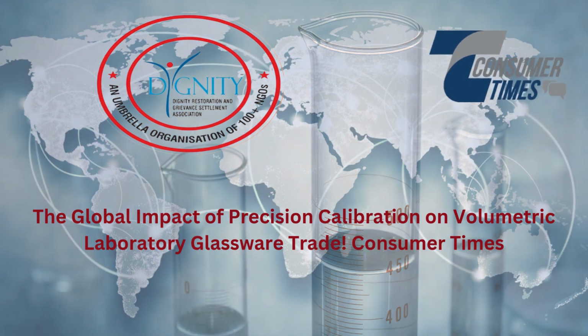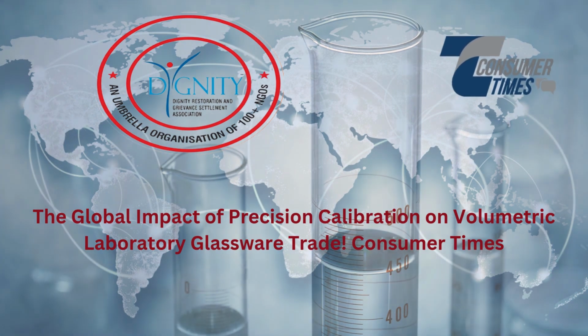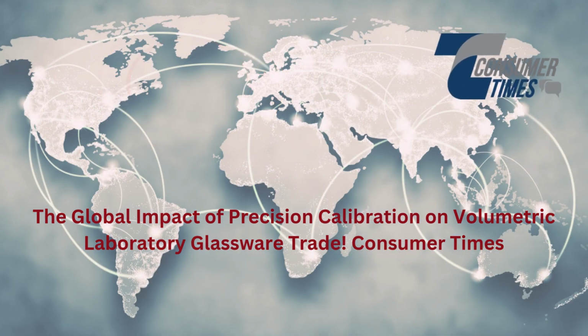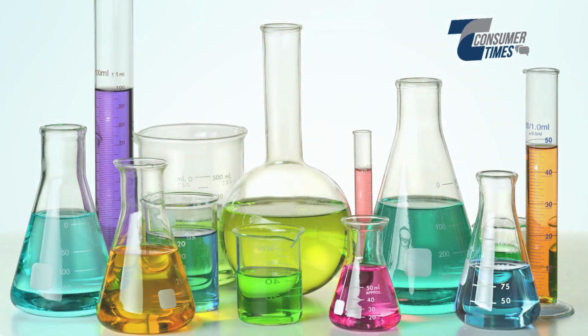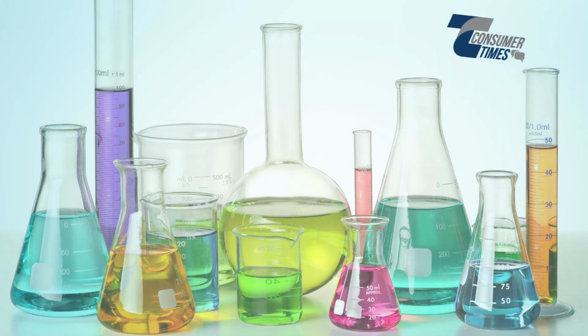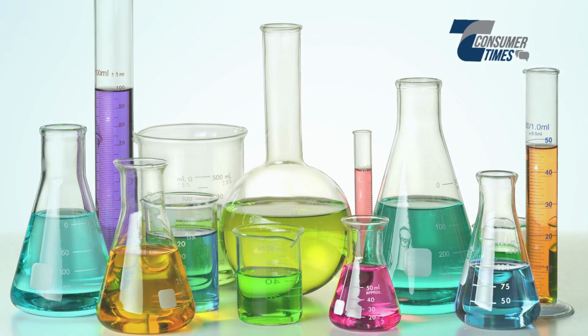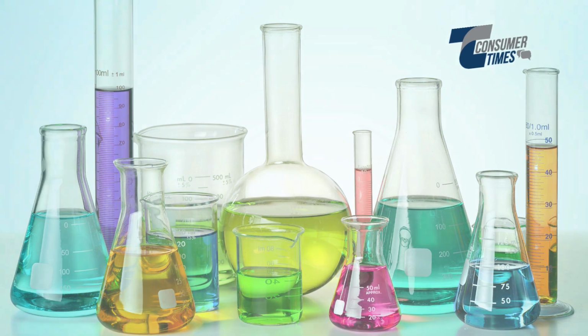Understanding precision calibration. Precision calibration is the process of verifying and adjusting laboratory instruments to ensure they measure accurately against a defined standard. Calibration standards are often traceable to international standards maintained by organizations such as the National Institute of Standards and Technology, NIST, or the International Organization for Standardization, ISO. The primary objective of precision calibration is to reduce measurement uncertainty, thus ensuring reliable results in scientific and industrial applications. For volumetric glassware, precision calibration involves measuring the actual capacity of the item against its nominal capacity. This is typically done using gravimetric methods, where water of a known density and temperature is used. The process requires sophisticated equipment and highly controlled conditions, underscoring its importance in ensuring the reliability of laboratory glassware.